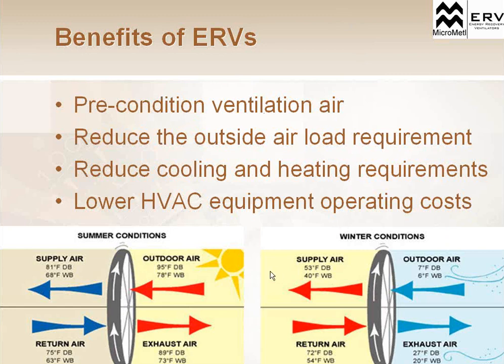So that's what we're doing when we say we're going to preheat or pre-cool that air. That's the precondition of the ventilation air, right? The fresh air that we would have to bring into a building to meet a ventilation code requirement, that's what we're doing here. We're pre-cooling or preheating that air with the exhaust air from the building. This is energy that we've already paid to heat or cool that air inside our building.